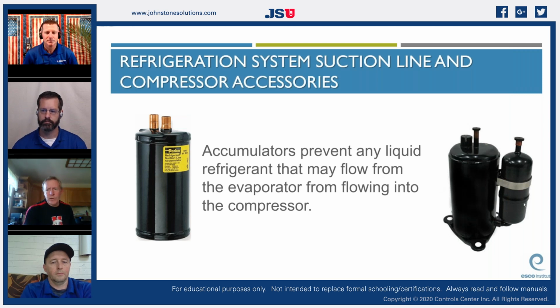This is an accumulator on the side of this rotary compressor over here. This is basically what techs are used to seeing in their heat pumps. You can usually get about 70% of the full charge in the accumulator. Yeah, they actually hold quite a bit of refrigerant because that thing may be running down to zero or lower temperature.